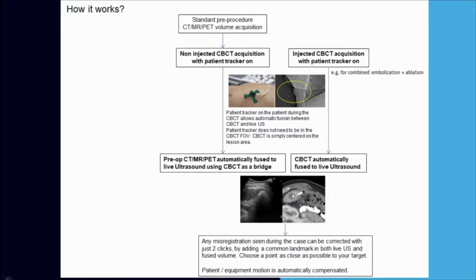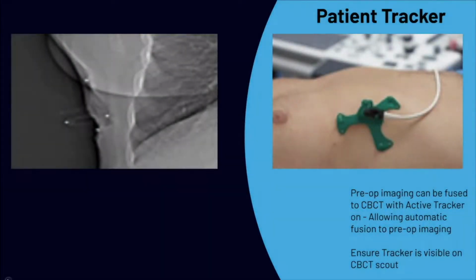And you get an image like this where you can see the mass here, but you may have a hard time seeing the mass on the ultrasound. Any misregistrations during this case can be corrected with a couple of clicks by adding some common landmarks on both the ultrasound and the fused volume. And that helps you get a really perfect alignment between your ultrasound image and your pre-procedural imaging study that you're using for targeting. So these are those non-enhanced cone beam CT images we were talking about.